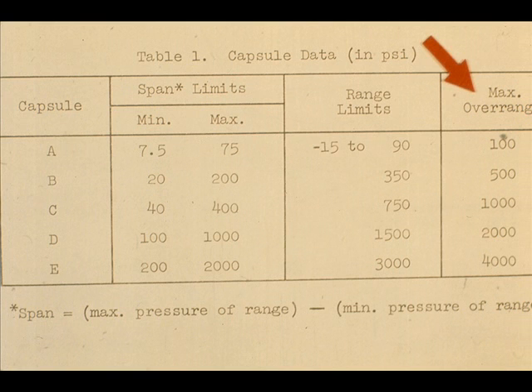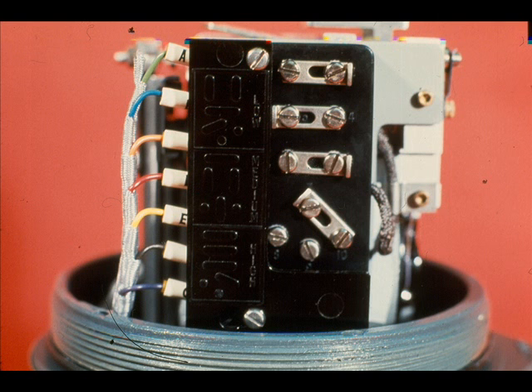Unlike the differential pressure transmitter, the pressure transmitter definitely can be damaged by overrange. Like the differential pressure transmitter, the links have to be set for the low, medium, or high span of a given capsule.